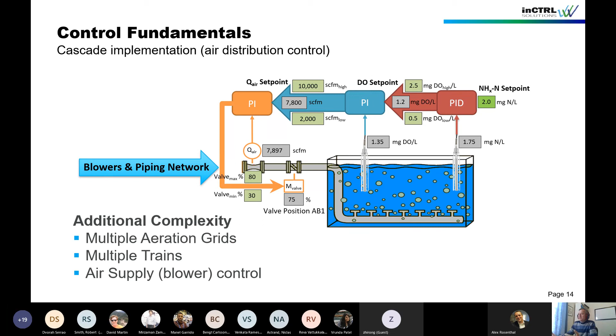So what you see here is the air supply, which is the blower control, typically based on pressure or airflow, total airflow. And then on the right-hand side, you have the air distribution control, and that is basically dealing with a lot of equipment from valves, pipes, and then also diffuser distribution, right? So very important. If you think you automatically get the air where you need the air, that is not true. In all our aeration control projects, we find that equipment and process are heavily limiting what's going on.